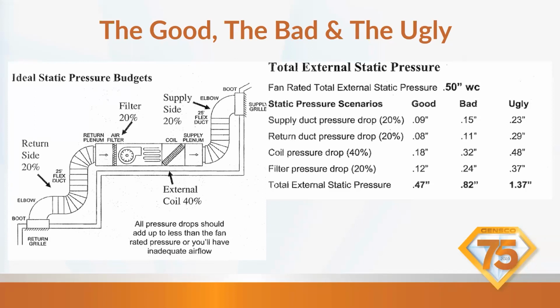Our blower chart tables only go up to 0.9, so keep that in mind. Our blower CFM charts only go up to a 0.9 static. So if you take that external static pressure and we're above 1 inch water column, we have return air or possible supply air issues. And then here's ugly: 1.37.